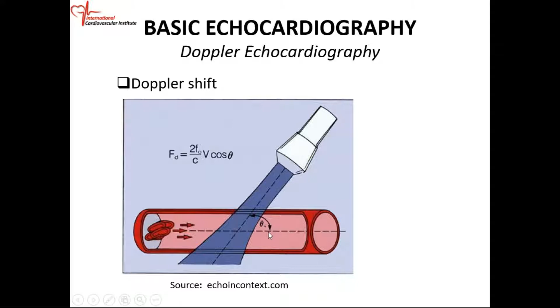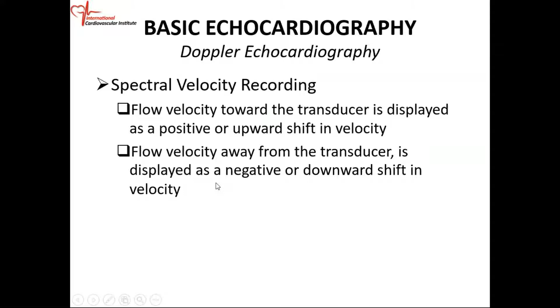The reason why you want to make the angle as small as possible is because of the cosine of the angle. Remember, the cosine of 0 is 1, the cosine of 90 is 0. So you'll get a much larger number if this angle is very small. Now we look at the spectral recording, how we get different spectral recordings. If the flow is towards the transducer, you're going to get a display on top of the baseline. It's going to be positive, an upward shift in the velocity. If the flow is away from the transducer, it's going to be below the baseline. So these are spectral drawings.